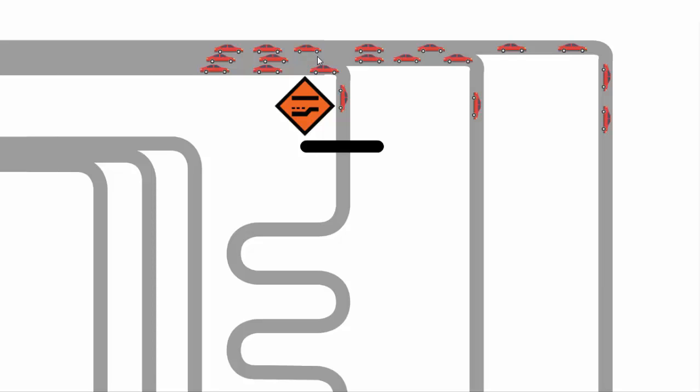In the zoning case, that is like closing a zone valve. And the issue is that, let's say we close one more road here. Now we have all of these cars trying to go down one road. And what that can cause, if that is water in a hydronic system, is actually an increase in velocity noise. And you can start to basically deadhead your pump, because unlike cars, the water is not being modulated at all if you have a single speed pump. So you're always sending this amount of cars or gallons per minute down the one road, and that can be stressful on a hydronic system.